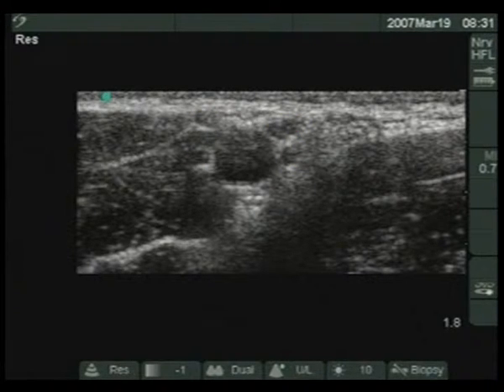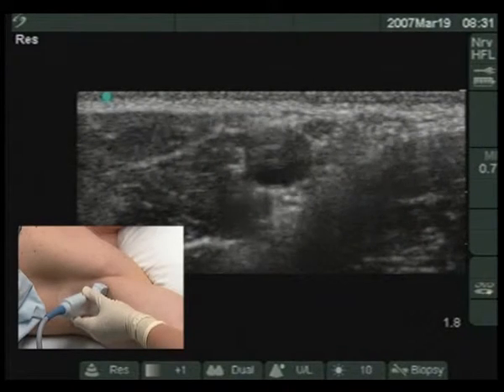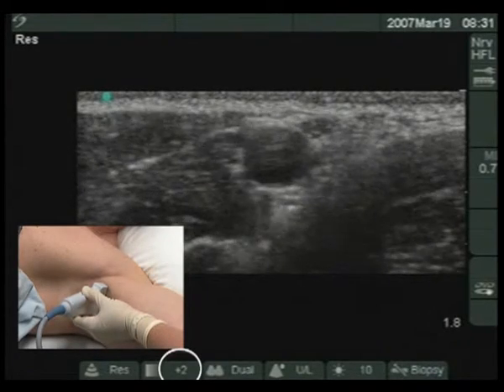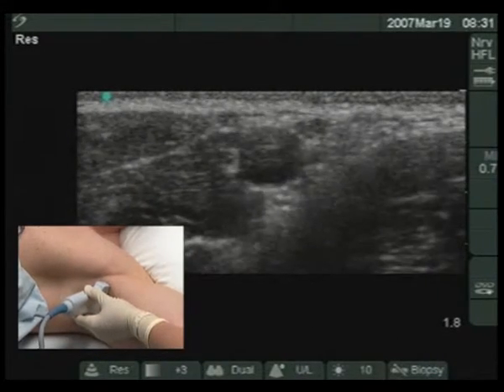Let us observe the changes in the quality of the image as we make some changes in the machine and probe settings. The grayscale is adjusted using the dynamic range button from 0 to +3. Note the difference in image quality.